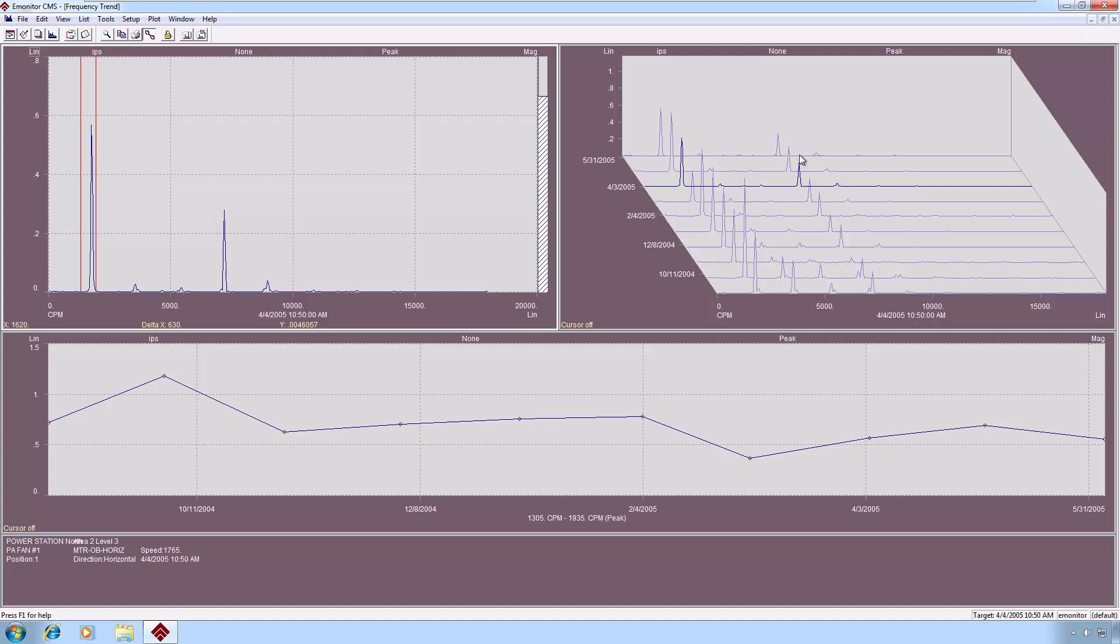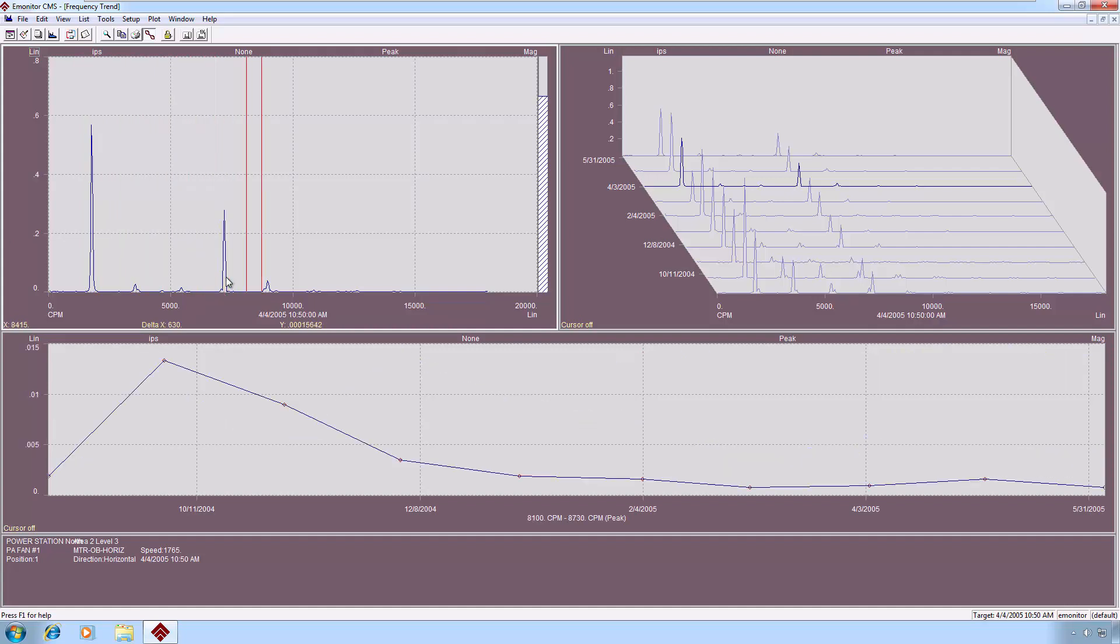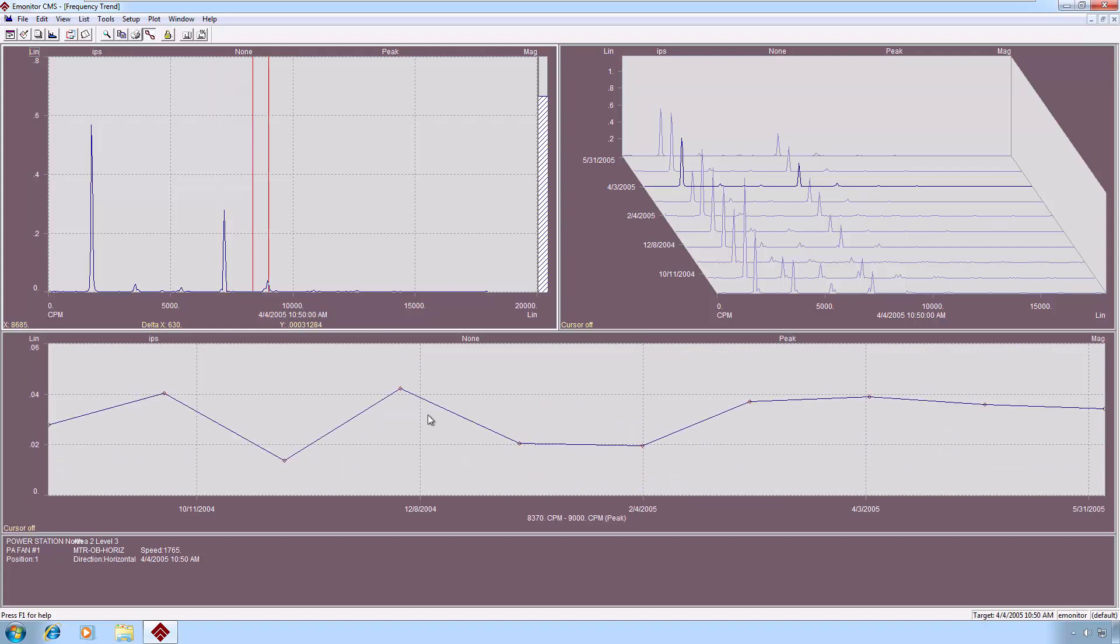You might be able to see it in the waterfall, depending on the density of the data that you're tracking in the waterfall. But you could also just simply draw a band with this particular plot view around the peak that included the haystacking below it. And then E-Monitor would show you the trend of the energy. And you'd be able to see very quickly whether or not that kind of haystacking has been going on for a long time.